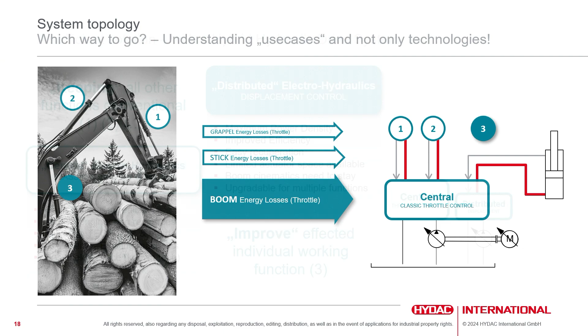So, of course, it is interesting to ask how we can get these losses down. Do we lower the pressure drop over the flow path? We looked into it. You can do a little bit about it, but that's not the major issue. The major issue is that we have to throttle the pressure down on that function over the valve. In cases like this, the easiest thing to do is to split up the circuits and put it maybe on a separate pump, so you can really operate it at a dedicated pressure level, and so you take out all these losses.